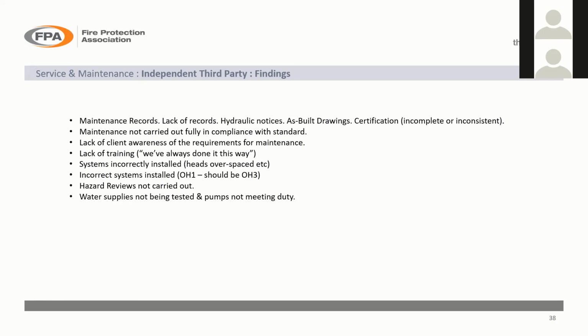The other one, of course, is water supplies where you've got a town's main fed system. It's important to test those at times of peak demand, so that you know that when everybody's running the taps at the same time as there's a fire, that you will have enough water coming into the system to put the fire out.